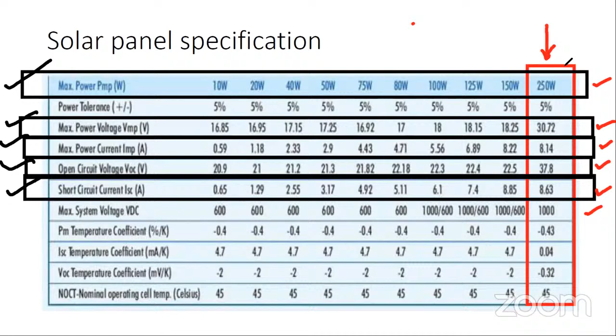Right. Now we are checking from the module point of view. The maximum system voltage VDC is given as 1000 volt. How many panels can be considered in one string? That will be the first question. To go for it, we must go to the PV module VOC.